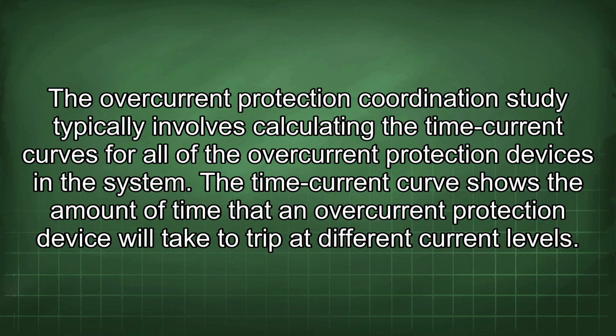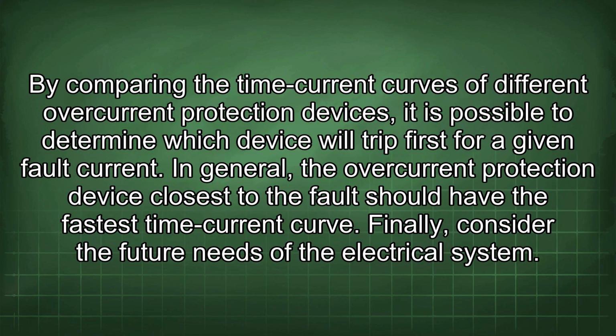The overcurrent protection coordination study typically involves calculating the time current curves for all of the overcurrent protection devices in the system. The time current curve shows the amount of time that an overcurrent protection device will take to trip at different current levels. By comparing the time current curves of different overcurrent protection devices, it is possible to determine which device will trip first for a given fault current. In general, the overcurrent protection device closest to the fault should have the fastest time current curve.